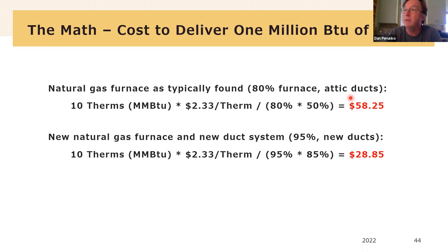So if you went into this particular house and swapped out their 80% furnace with a 95% furnace and replaced the duct system, making a smaller duct system and burying it in insulation, you could lower that loss from 50% to 15%. The loss portion in the ducts was half. Now it's only 15%. So you now have 95% combustion efficiency, 85% duct system efficiency. The energy cost for your 1 million BTUs goes from $58 to $28. What this is illustrating is that even with lower efficiency machines like gas equipment, the whole system is incredibly important, right? If it's a ducted system, you have to deal with the equipment and the system, the ducts, in order to get to a good end goal.